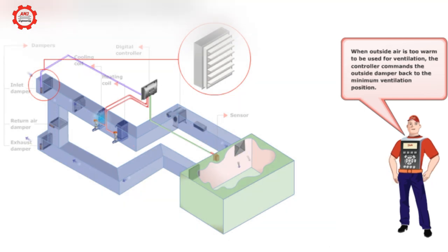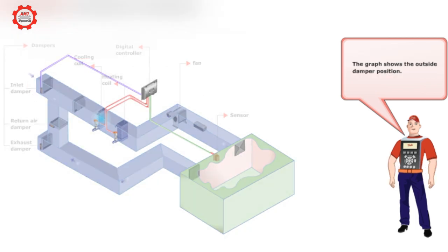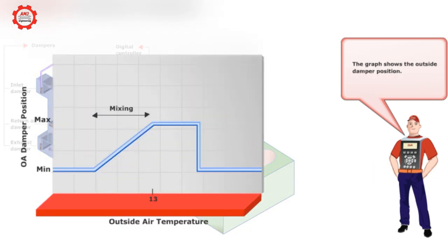When outside air is too warm to be used for ventilation, the controller commands the outside damper back to the minimum ventilation position. The graph shows the outside damper position.